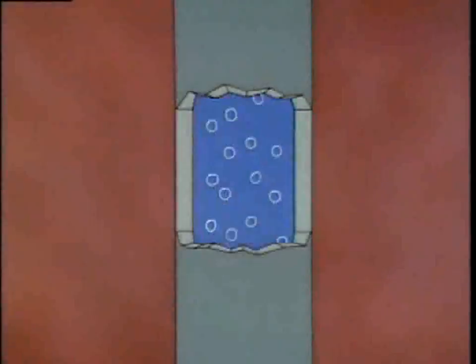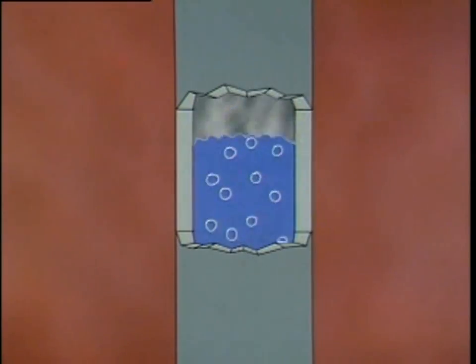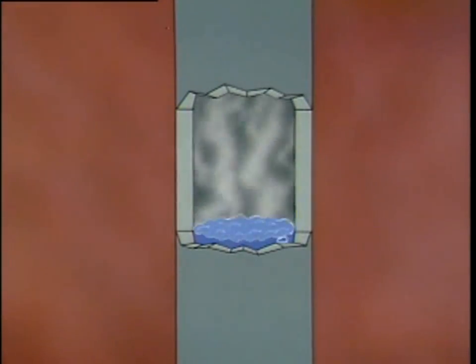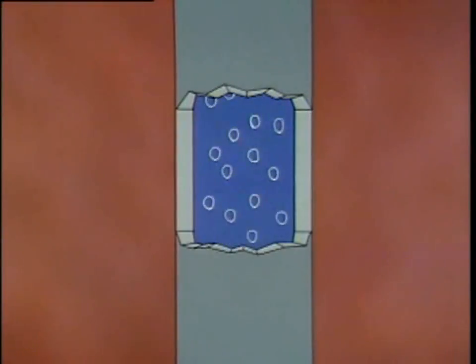A heat transfer problem can also occur if the feed water supply stops for any reason. Without a continuous supply of feed water, the boiler may boil dry. With no water to remove the heat, the tube metal rapidly overheats and severe damage may result. In boilers that burn coal or oil, another problem that can affect heat transfer is the buildup of soot, created by ash and unburned fuel particles in the combustion gases.